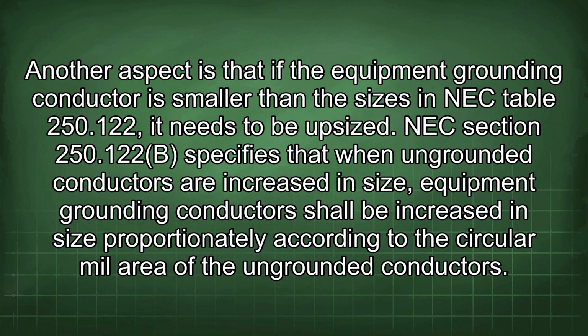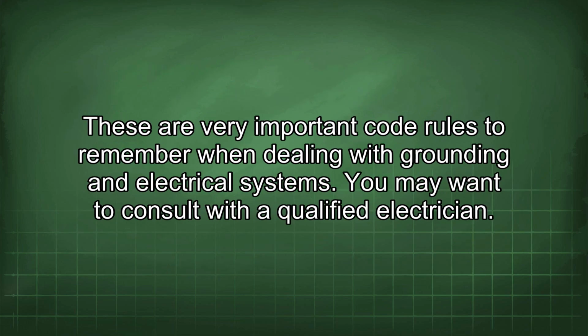NEC Section 250.122(B) specifies that when ungrounded conductors are increased in size, equipment grounding conductors shall be increased in size proportionately according to the circular mil area of the ungrounded conductors. These are very important code rules to remember when dealing with grounding and electrical systems. You may want to consult with a qualified electrician.